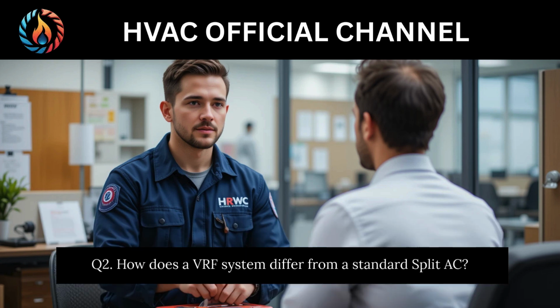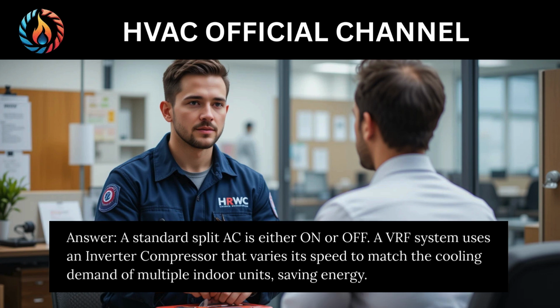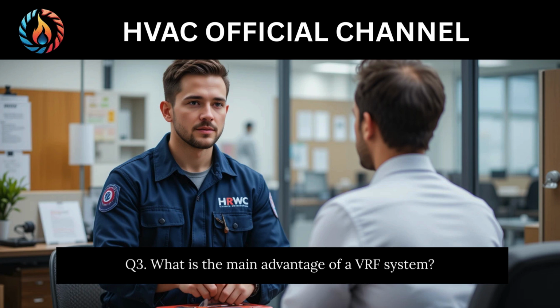Q2. How does a VRF system differ from a standard split AC? Answer. A standard split AC is either on or off. A VRF system uses an inverter compressor that varies its speed to match the cooling demand of multiple indoor units, saving energy.